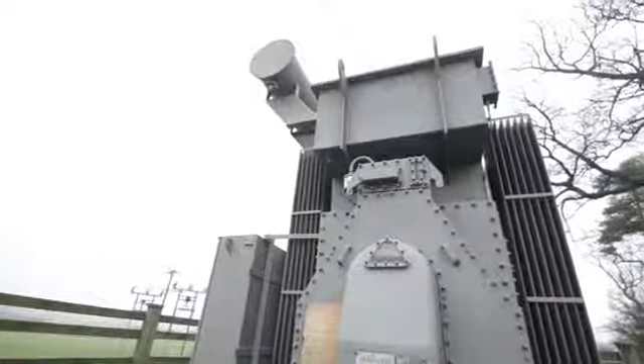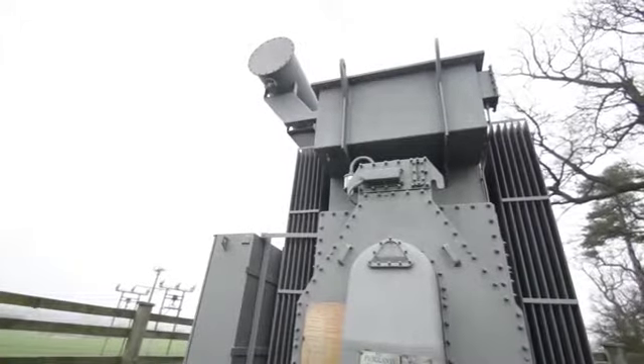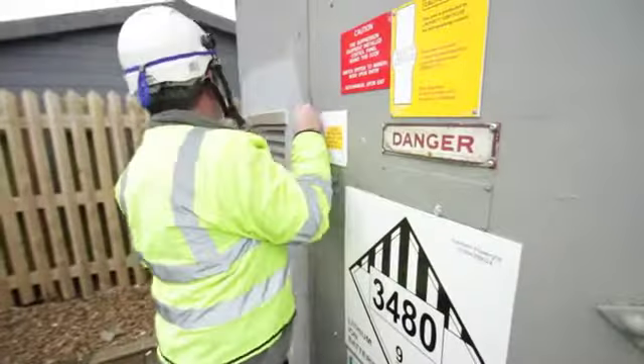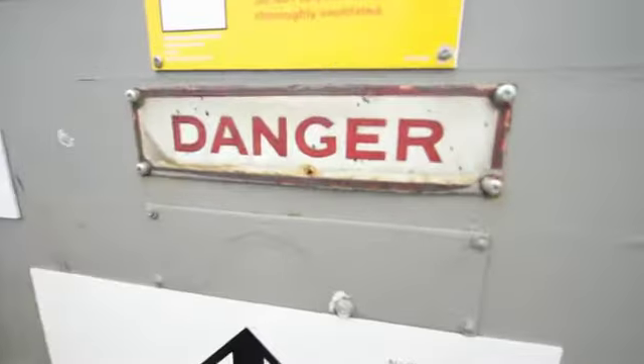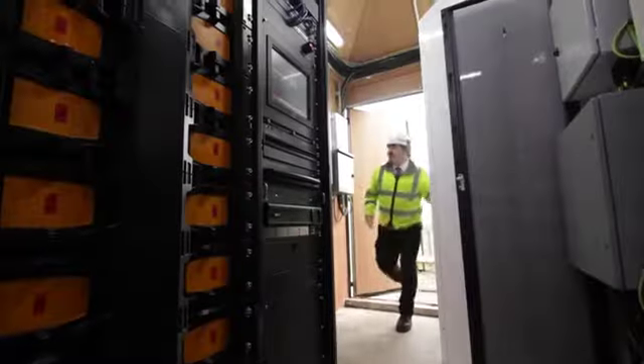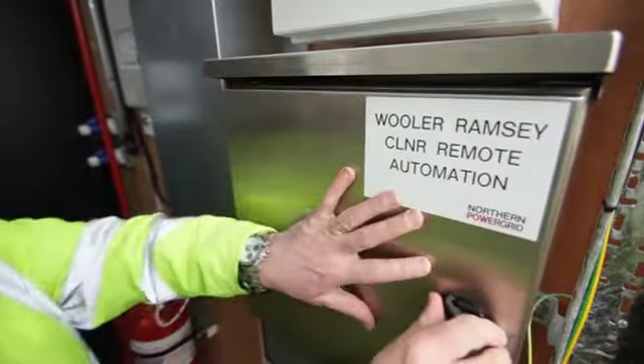Traditionally on our rural networks, we feed electricity the same from a primary substation. However, it feeds over a much greater distance, predominantly by overhead lines. Our limiting factor on the end of those overhead lines isn't power flow anymore, it's all about controlling the voltage and keeping it within tight statutory limits.